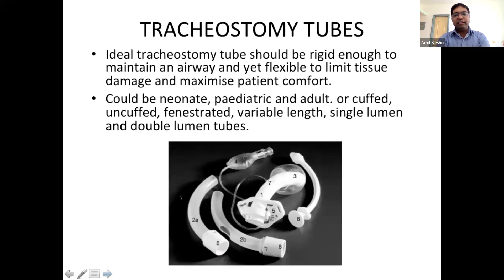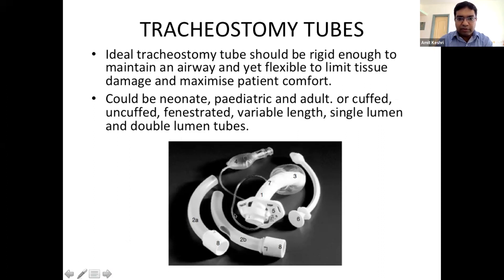With this physiology in mind, the ideal tracheostomy tube must be rigid enough to maintain an airway — so it does not collapse — yet flexible enough to limit damage and maximize patient comfort. Tubes can be neonatal, paediatric, or adult, and may be cuffed or uncuffed. A standard cuffed tube has a cuff, a pilot balloon, an inner tube, and a connector for oxygen or filters. There are also fenestrated tubes with outer and inner cannulas, and an introducer.